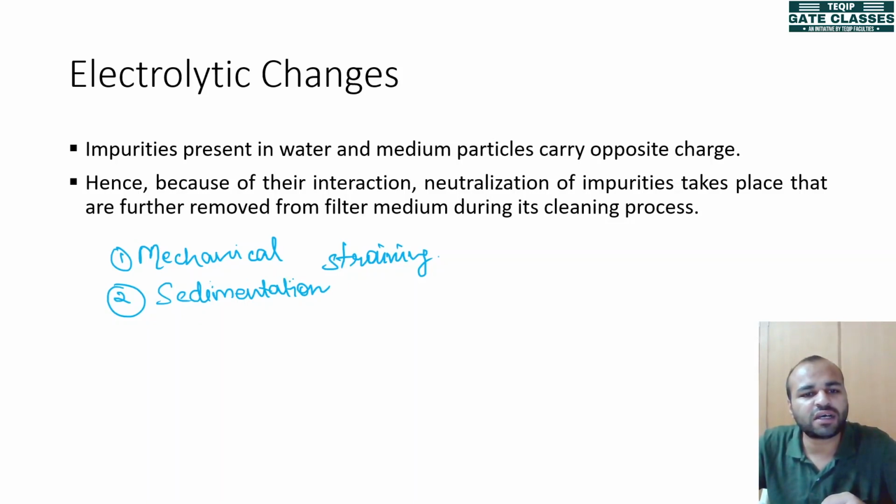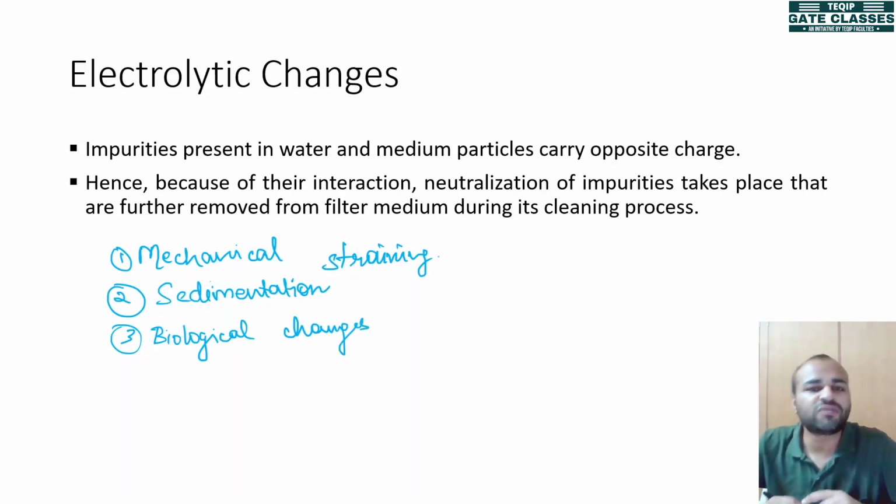The water is no longer turbulent and hence particles also get settled down due to the process of sedimentation. The third process or phenomenon that is occurring in the filtration system is regarding the biological changes. In biological changes, what did we study? That there is a growth of a layer known as Schmutzdecke in which the partially decomposed organic matter is getting completely decomposed by the microorganisms.